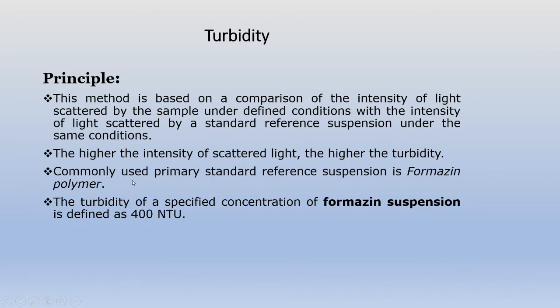Here we are using the primary standard reference suspension, formazine polymer. The turbidity of the specified concentration of this standard reference is 400 NTU, nephelometric turbidity units.